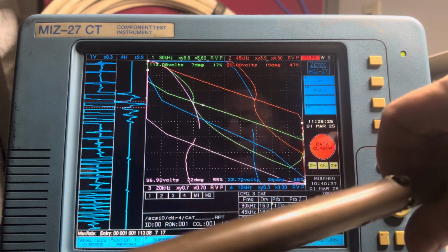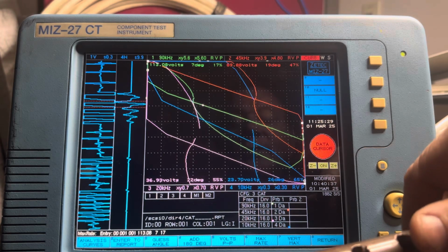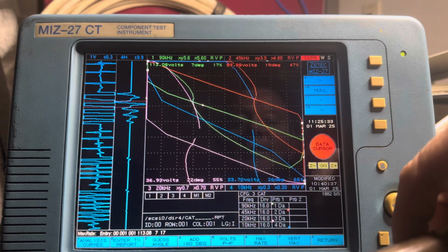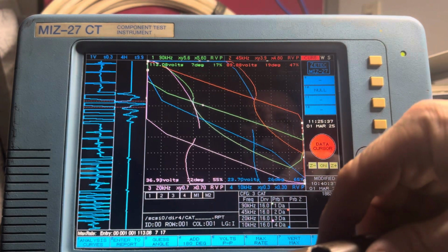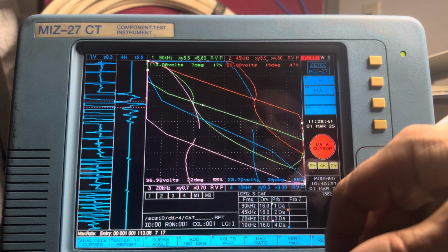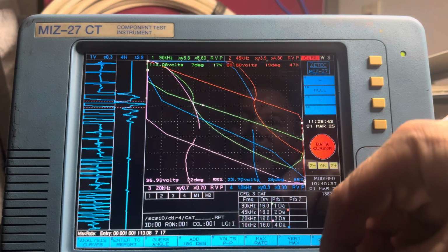So hopefully by this demonstration, you can see that the larger the hole, more eddy currents close to the surface are disturbed, and that will drop your phase. So just because you got a signal that's quite a bit less phase than what you set your 100 at, don't think that that can't be a big 100% hole, because it is.